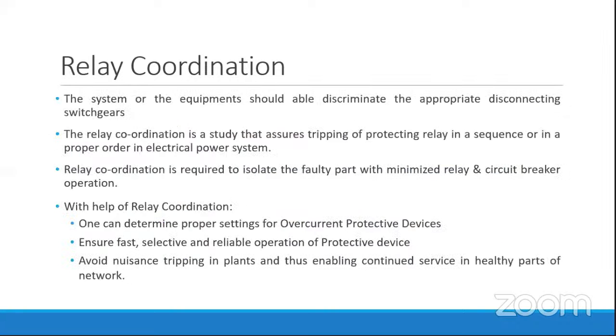Moving further, as I said, the system or the equipment should be able to discriminate appropriately, and should disconnect the feeder and the switchgear associated with the feeder at which the fault occurs. Relay coordination is a study that ensures the tripping of protective relays in a sequence, or a proper order, in the electrical system.